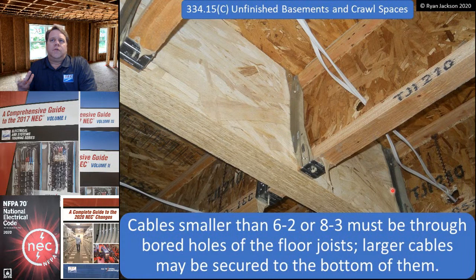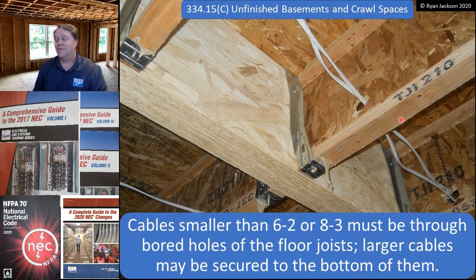We also have some requirements for unfinished basements and crawl spaces that say cables smaller than 6/2 or 8/3 must be installed through bored holes of the floor joist. Larger cables, however, can be secured to the bottom of the joist. Here in my area, we use engineered wood joists, and it makes it nice and easy. Those of you electricians that still have 2x10s and 2x12s, you have no idea what you're missing. These holes here are pre-drilled. You don't even need a drill when you wire a house. Well, you do for the upstairs. But you just run these things through the perforated holes, done deal.